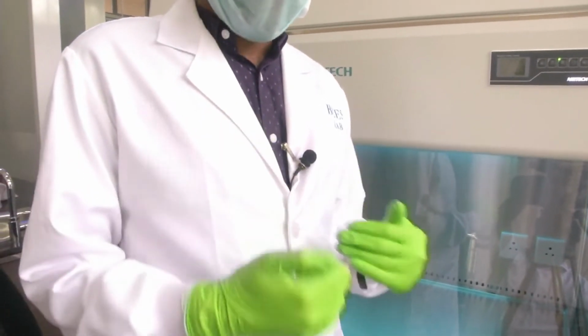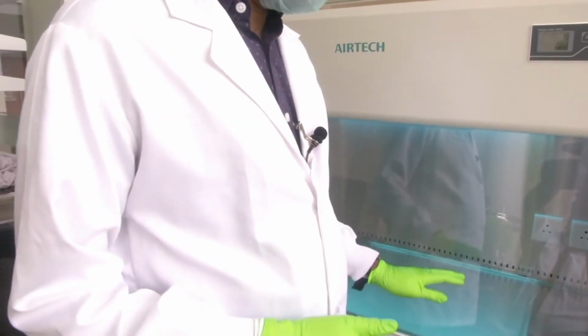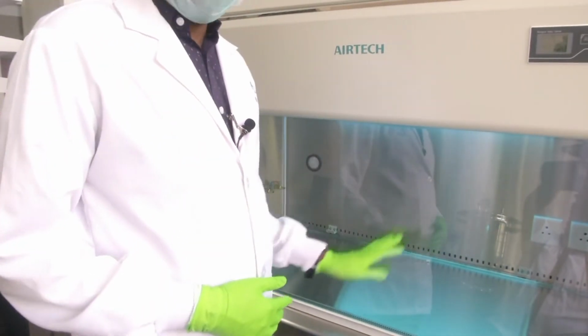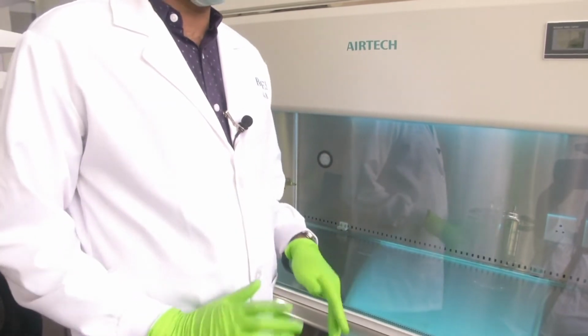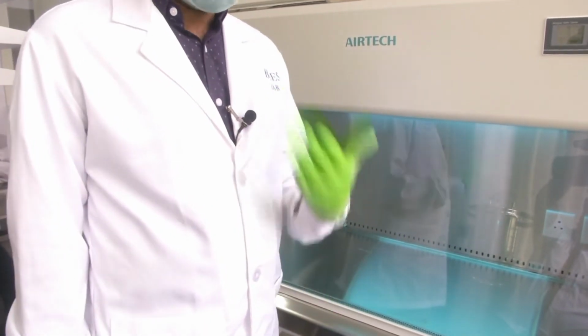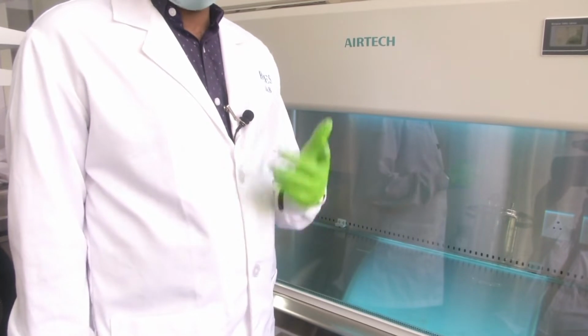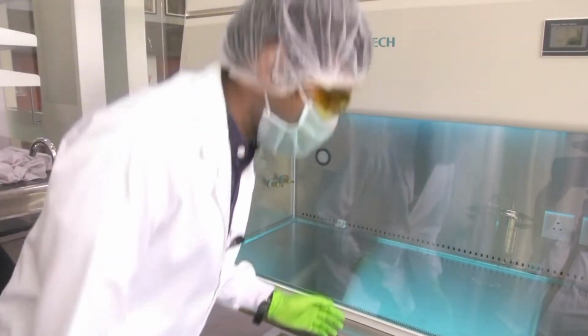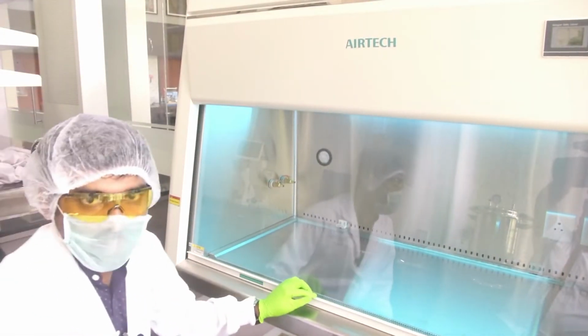Whenever we are not using the biosafety cabinet, the UV light should be on so that it will sterilize and kill any pathogenic or bacterial growth that might happen inside the biosafety cabinet, so that the sterile environment is maintained sufficiently well inside the biosafety cabinet at all times whenever we are not using it. But as you all know, we should not get exposed to UV light. So this biosafety cabinet provides that protection also.